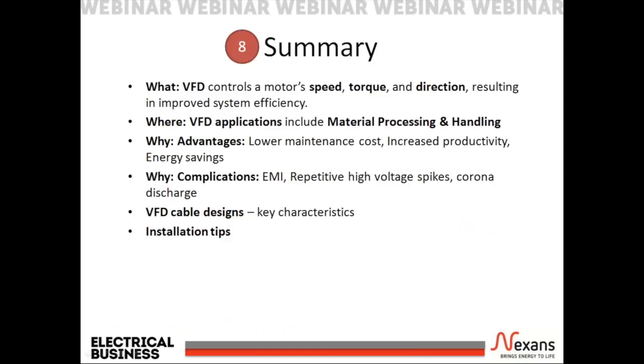In summary, a VFD controls a motor's speed, torque, and direction, resulting in improved system efficiency. VFD applications include material processing and handling. The advantages of VFD systems include lower maintenance cost, increased productivity, and energy savings. The complications of VFD systems when proper cabling is not used include EMI, repetitive high voltage spikes, and corona discharge.